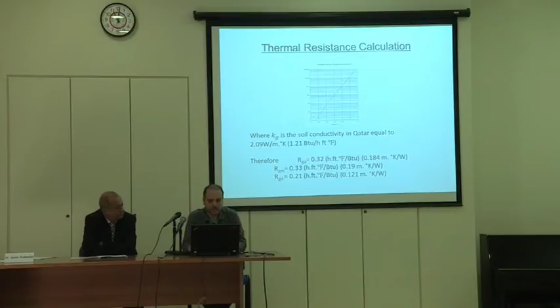Once we have those equivalent thermal resistances, we have to identify the net heat that's either injected or taken from the ground throughout a year. Because if we're injecting heat within the ground during the summer, and we're taking heat from the ground during the winter, then the yearly balance would be 0, and our system would be steady throughout the years. But similar to our case, where we're just injecting heat during the summer, then after a certain period of time, let's say 10 or 15 years, the temperature of the ground will change, and the effectiveness of our system will decrease. So also we took that into account.